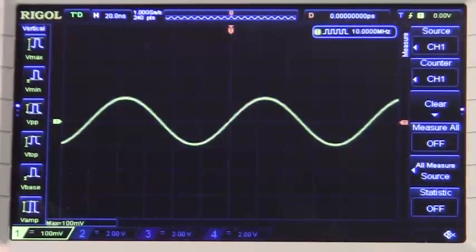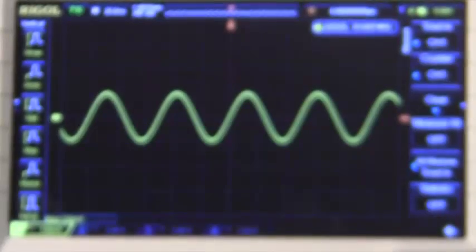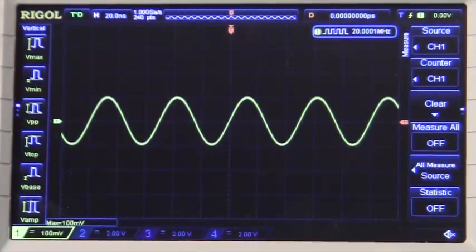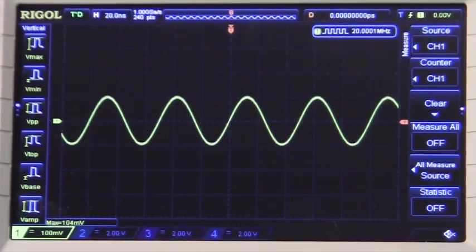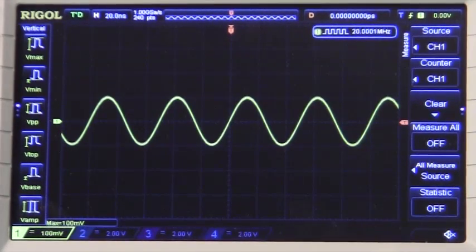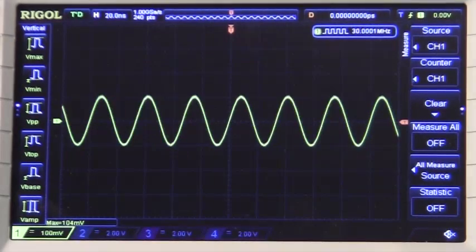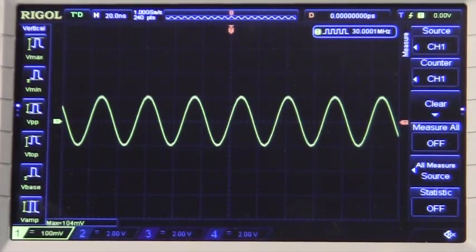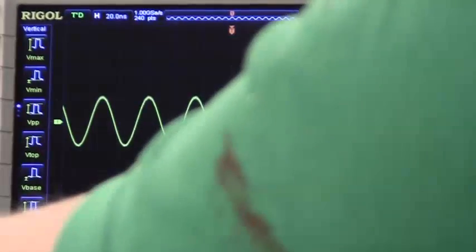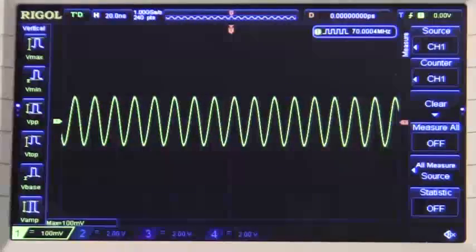Okay, and now I will change the frequency to 20 MHz like this, and the output level measured by the scope is 104 mV. And then I will continue like that, all the way. Still 104 at 30, at 40 MHz, and we'll continue to 80 MHz.